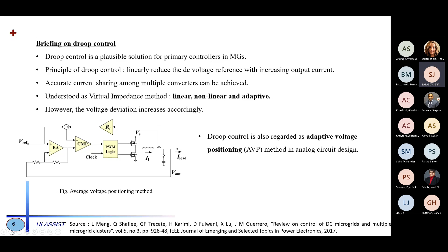This is realized through a virtual resistance behind the source, which gives power sharing accurately proportionate to the current rating of the converter. But there's a trap: when we try to achieve accurate current sharing, we cannot regulate the voltage, because there's a voltage drop across this virtual impedance. Hence, the role of secondary controllers becomes important.